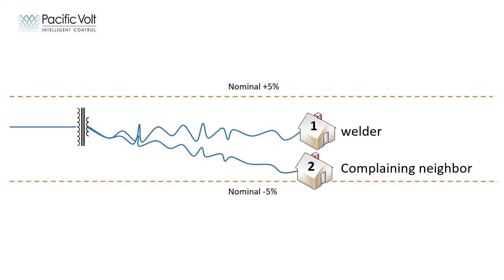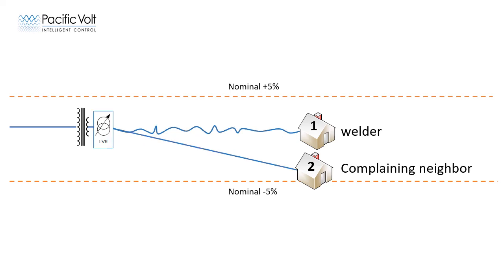If two houses are connected on the same transformer, a large, rapidly fluctuating load at house 1 can cause flicker complaints at house 2. Where you insert the LVR will affect the two houses differently. Keep in mind that the rapidly changing load at house 1 is causing a voltage drop in both the transformer as well as in the secondary conductor feeding house 1.